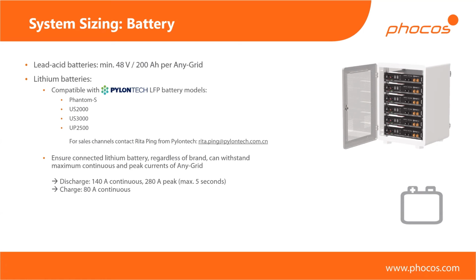For the system sizing, one of the first things is obviously the battery size, if you do use a battery. And I think the most important thing to keep in mind there is the minimum battery size. If you're using lead-acid batteries, regardless of whether they're gel, AGM, or open type liquid electrolyte batteries, we recommend at least 200 amp hours per unit. So if you're using 2 units, you need to have at least 400 amp hours for the 48 volt system.